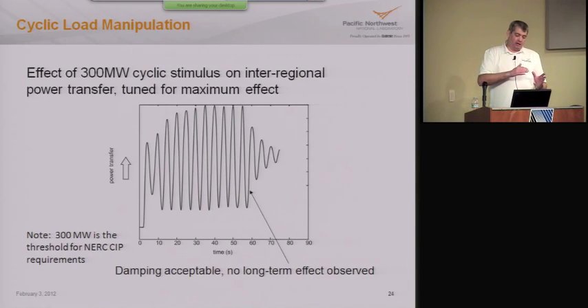And we looked at tuning it to the right frequency. This particular plot is megawatts across an interface. You can clearly see that there's a lightly damped oscillation, but it was stable. It wasn't a growing oscillation. And then when we turned off the stimuli, it quickly damped out and the system recovered.